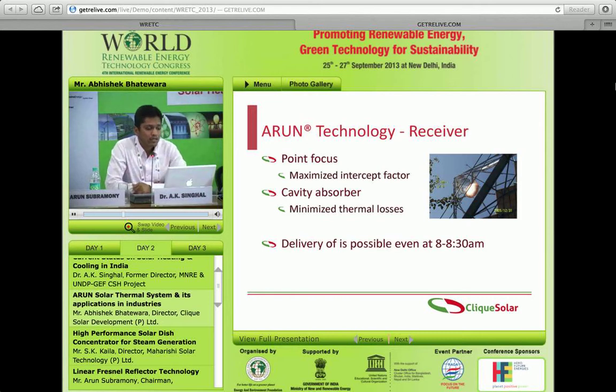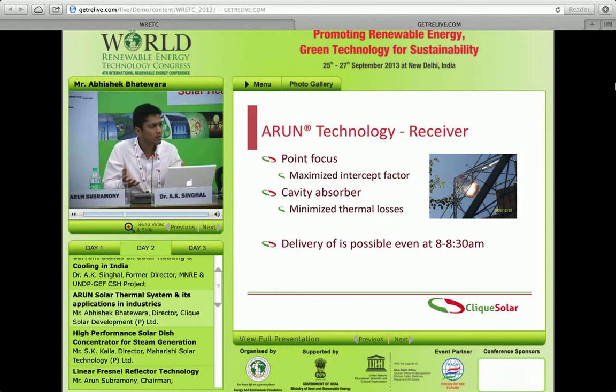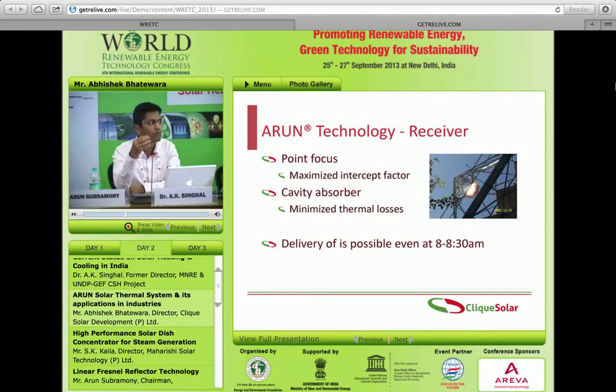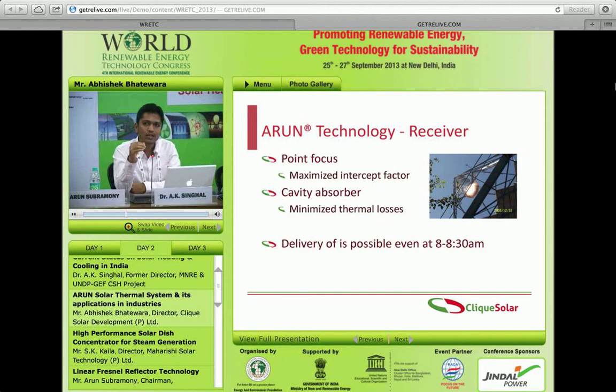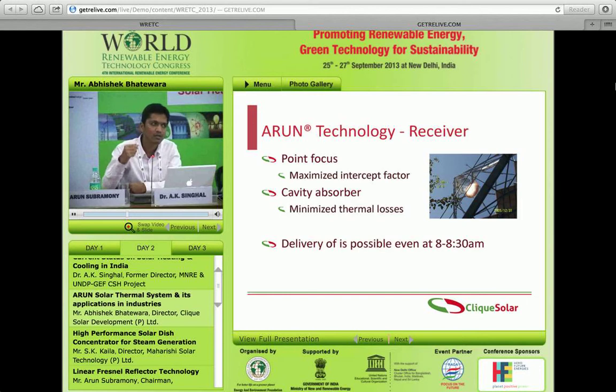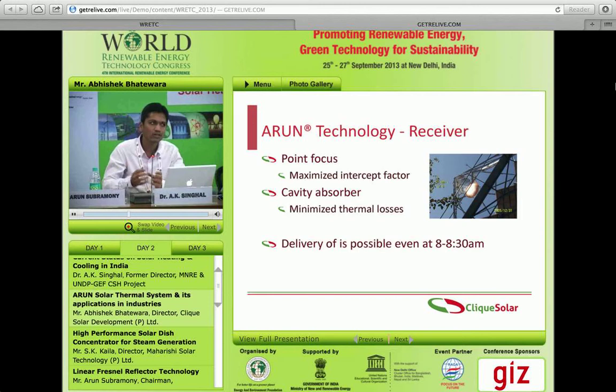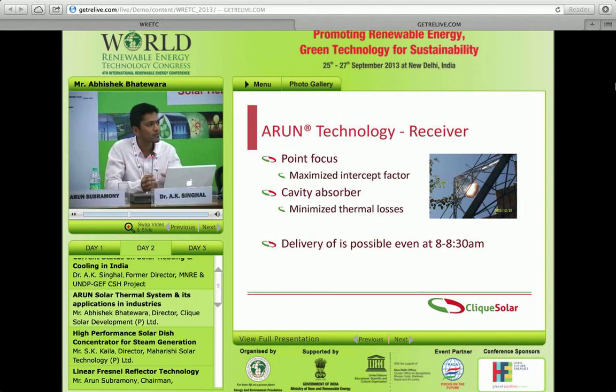The second aspect of the technology is the receiver — the point at which all sun rays are concentrated. You need to extract that energy efficiently, ensuring minimum thermal losses. We designed a cavity-shaped receiver; because it is cavity-shaped, hot air tends to rise and all energy is trapped inside. The efficiency of this receiver alone is about 95 percent, meaning almost 95 percent of the energy entering the receiver is utilizable.